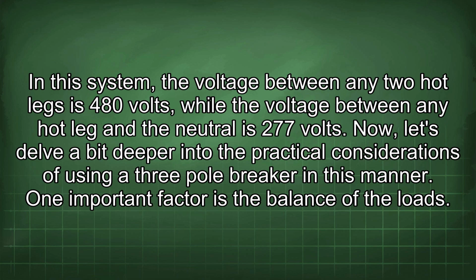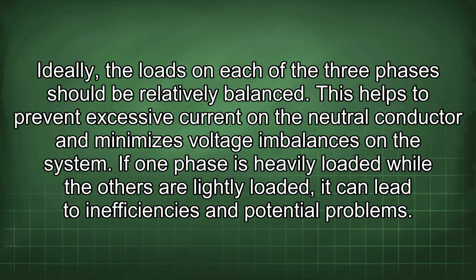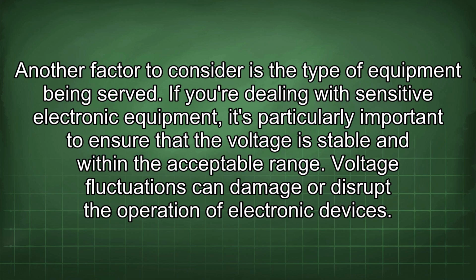Now let's delve a bit deeper into the practical considerations of using a three-pole breaker in this manner. One important factor is the balance of the loads. Ideally, the loads on each of the three phases should be relatively balanced. This helps to prevent excessive current on the neutral conductor and minimizes voltage imbalances on the system. If one phase is heavily loaded while the others are lightly loaded, it can lead to inefficiencies and potential problems. Another factor to consider is the type of equipment being served. If you're dealing with sensitive electronic equipment, it's particularly important to ensure that the voltage is stable and within the acceptable range. Voltage fluctuations can damage or disrupt the operation of electronic devices.